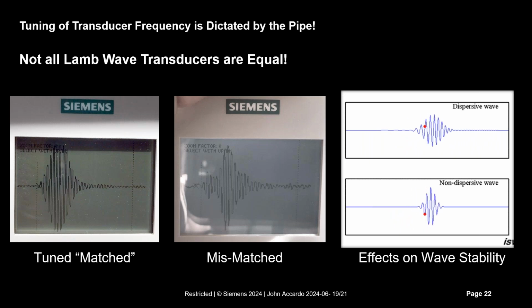And if you look really, really closely where my mouse is, there's an X, and that's identifying the first cycle of the waveform, or the arrival point of the waveform. And that's arrived at through the wave shape by predicting the slope angle of the front end of the wave. Where it crosses through zero, we can identify the arrival of the received signal very precisely. And that wave will not change. So if you change your fluid in your pipe, and now you had say gasoline in your pipe with a speed of sound of 1250 meters per second, and now you have diesel fuel with a speed of sound of 1370, your signal is going to arrive later in time because the speed of sound is slower. And all that's going to happen is that received signal is going to move, like you see on the bottom on the right, but the shape won't change. So we can maintain the measurement without any sacrifice of accuracy.